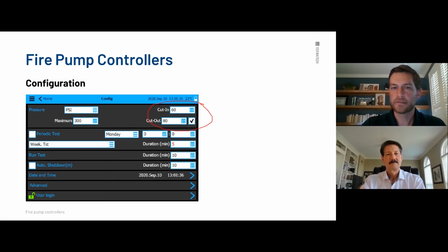What we're doing here is having you select the cut in and then automatically doing just 10 PSI above that for cutout. It's just a factory default. If you want to have your cutout set differently than that, you just push that check box, that clear box there, and it'll put that check mark in, which then allows you to modify the cutout. So you can set the cut in and cut out to whatever you want based on the system requirements. But just a note on that, we do have it set to where cut in is the only thing you have to enter, and it automatically populates a cutout 10 PSI above that.